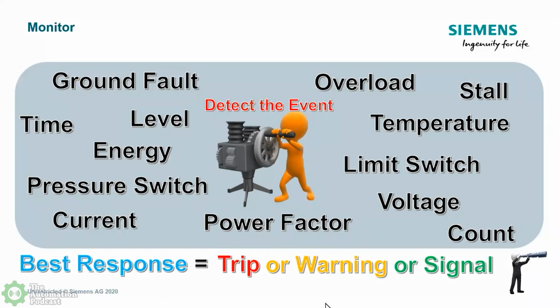And then of course our trip. Trip also has a bit toggle. It sends to the web page, lets it know that we have a trip, and gives you words and says overload, or here in a minute I'm going to demonstrate what I call a fault that comes up if you have an execution stop command where you told the starter to stop, but it continued to have current flowing. But the trip, of course, means everything's going to shut off and so forth. But you have the ability to set those up yourself, and it's very, very flexible.